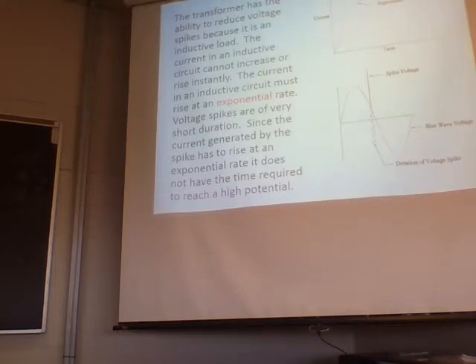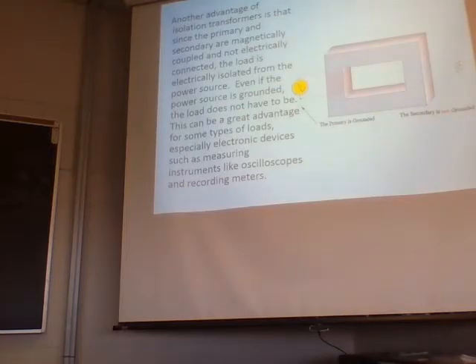Another advantage of isolation transformers is that since the primary and secondary are magnetically coupled and not electrically connected, the load is electrically isolated from the power source. Even if the power source is grounded, the load does not have to be. This can be a great advantage for some types of loads, especially electronic devices, such as measuring instruments like oscilloscopes and recording meters.